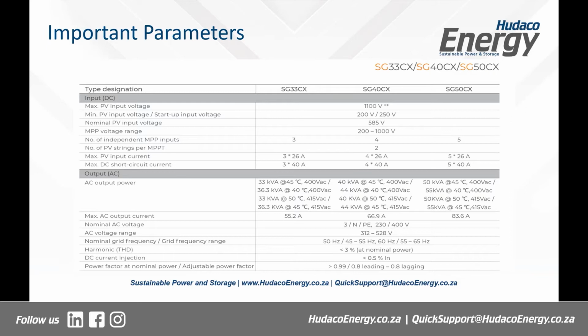On the 50CX there are 5 MPPTs, and each MPPT can take 2 inputs, meaning you can put in about 10 strings. There's also a limit to the current you can put in, 3 by 26 and 5 by 26 as described. These parameters are very important for designing, so you know exactly how many strings you can put in and how much current is allowed into the inverter without risking blowing it or other attached equipment.